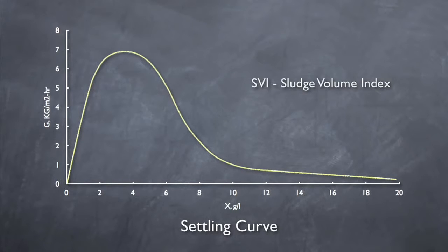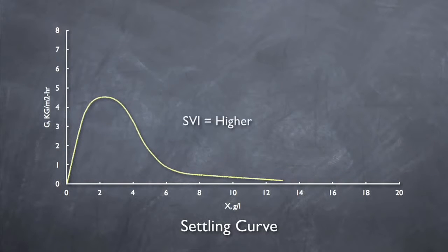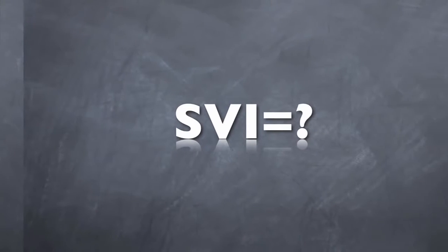A smaller SVI, which represents faster settling, results in a larger settling curve. A higher SVI, which represents slower settling, results in a smaller settling curve. So what does it matter if the curve is larger or smaller? Well, we'll find that out in a minute. But now that we know that SVI is important in determining the settling curve, how do we determine the SVI, and what causes it to change?